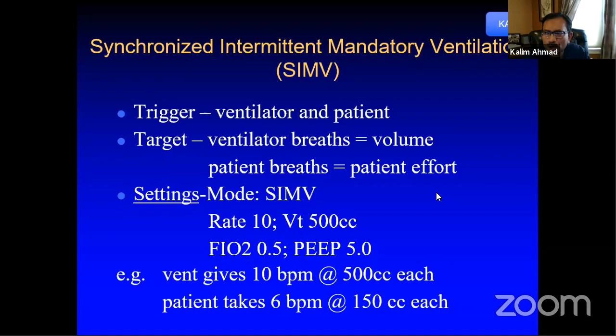Machine is going to give, no matter what, this amount. But if the patient decides to take extra 6 breaths, this time the amount of air that moves with that patient-triggered breath is going to be variable. It's going to depend upon how much strength the patient's negative pressure has to get tidal volume. So it could be 150, 250, 450, 600, 800, depending upon the compliance of the patient, how the lung is either stiff or compliant.